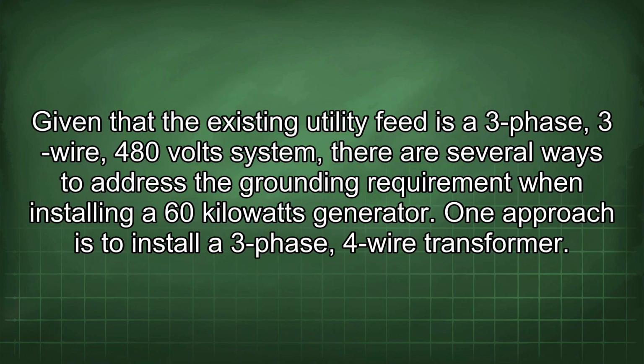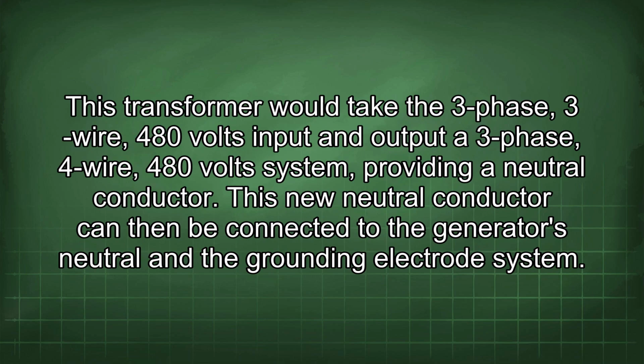Given that the existing utility feed is a three-phase, three-wire, 480-volt system, there are several ways to address the grounding requirement when installing a 60 kW generator. One approach is to install a three-phase, four-wire transformer. This transformer would take the three-phase, three-wire, 480 volts input and output a three-phase, four-wire, 480-volt system, providing a neutral conductor. This new neutral conductor can then be connected to the generator's neutral and the grounding electrode system.